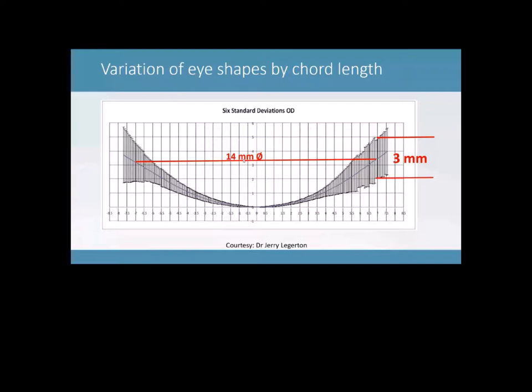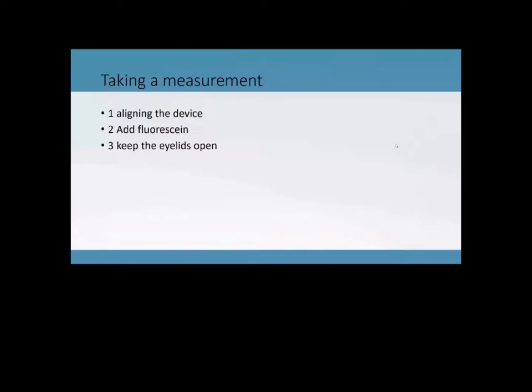Imagining what if you're measuring up to 16, 17 millimeter, that diversity is going to go even bigger. But lucky for us with the device we have, we're able to actually measure that far. So we're not extrapolating, we're getting actual data on that part of the eye. So this slide is just in here to show you guys how important it is to gather actual data and don't start extrapolating.